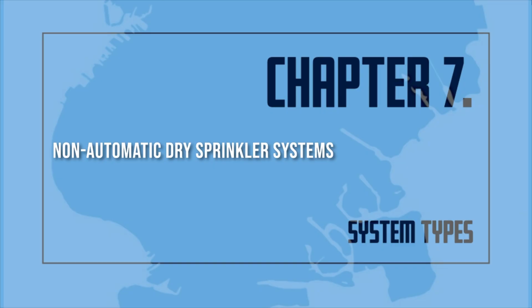1. Perforated pipe systems, a single line of piping drilled at intervals for water discharge. These systems are usually found in basements or other areas difficult to reach in firefighting operations. 2. Open fixed spray nozzles for transformer vaults or other hazardous areas. 3. Exterior exposure sprinklers or window sprinklers use open sprinkler heads to form an external water curtain on the walls of a building. And 4. Foam supply systems are used for the protection of special hazardous occupancies.